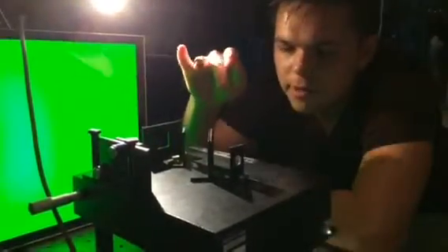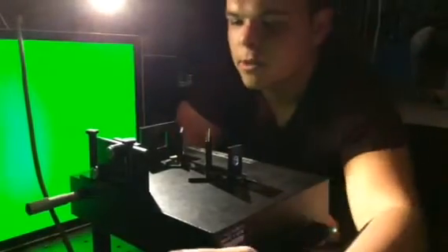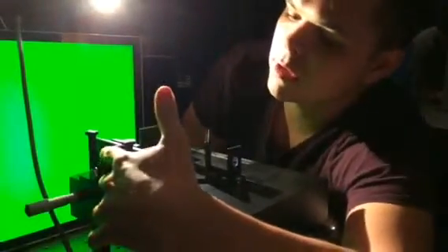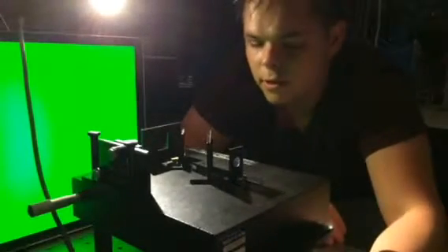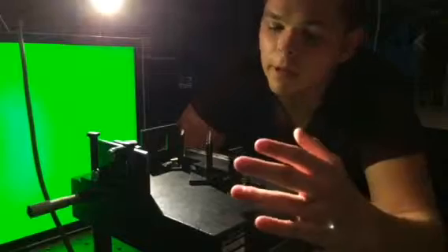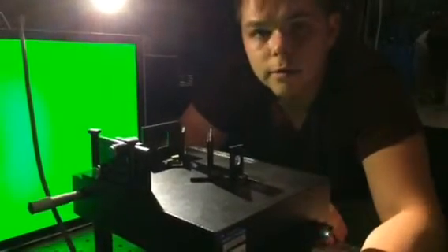Here we have a Michelson interferometer with our monochromatic green light source, and on it we have our beam splitter, compensating plate, and two mirrors. We can adjust the position of one with this and the tip and tilt of the other one. If the mirrors are parallel but with a different optical path length, we get circular fringes at the output, and if they're not parallel but have the same optical path length, then we get linear fringes.